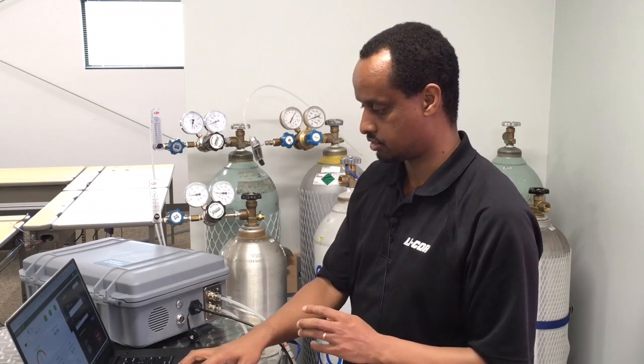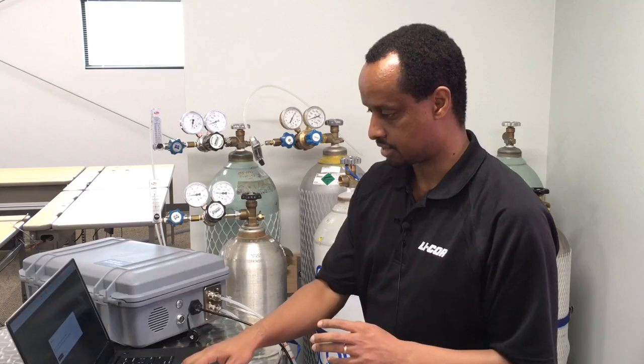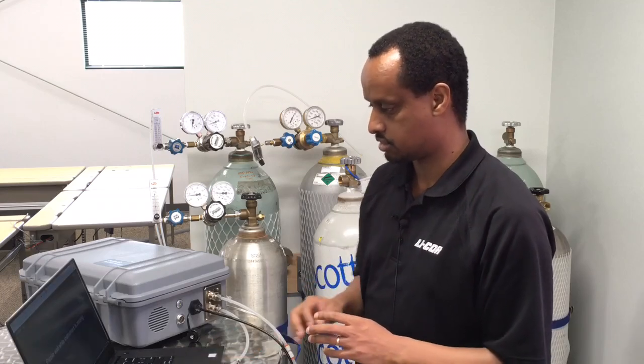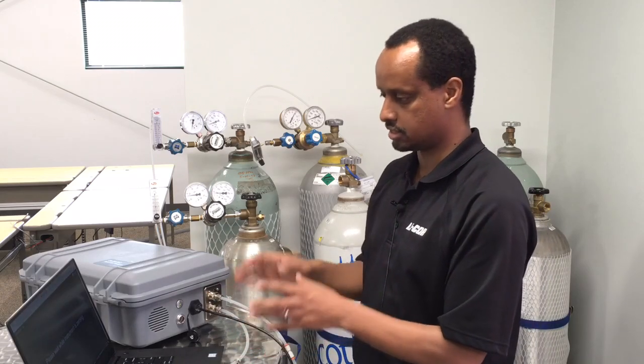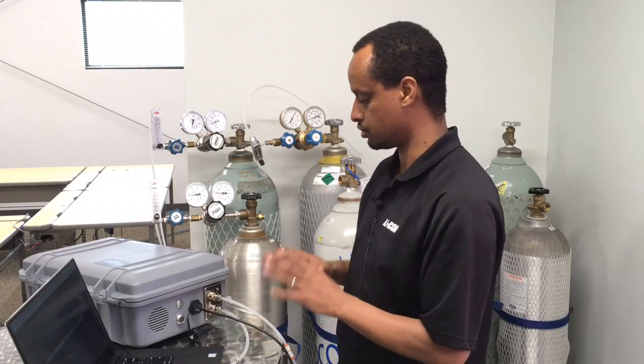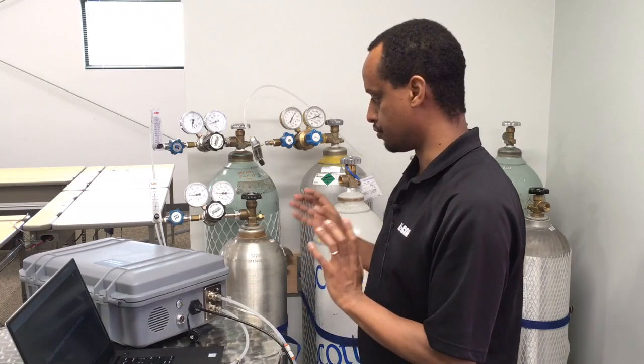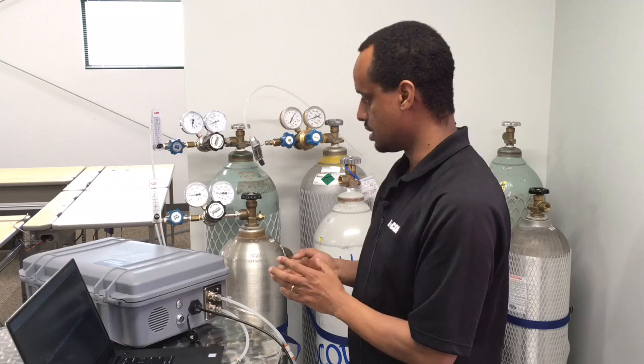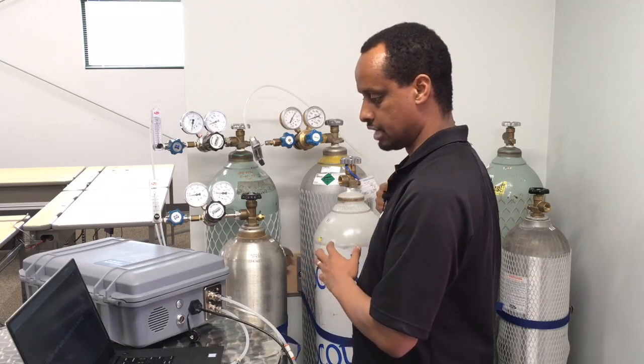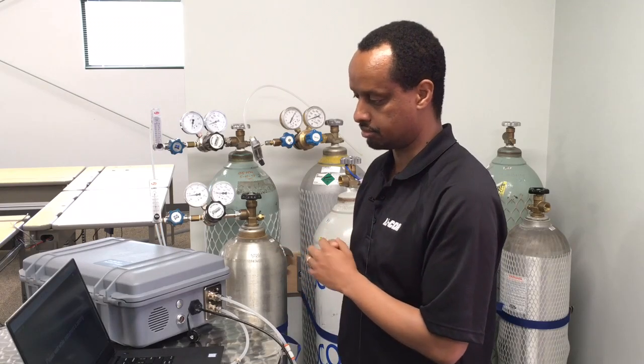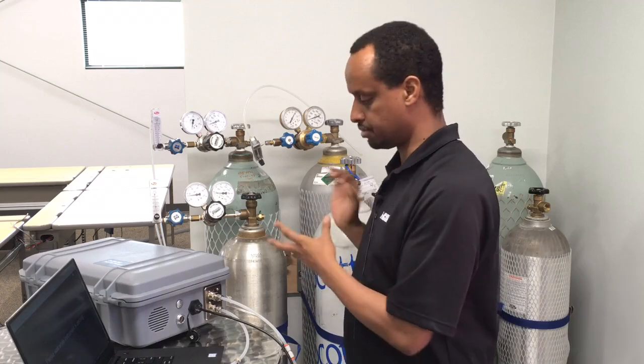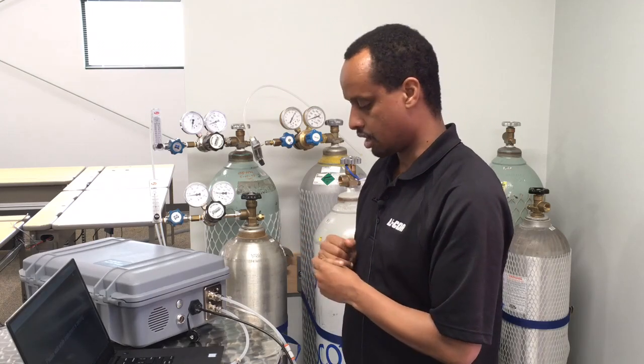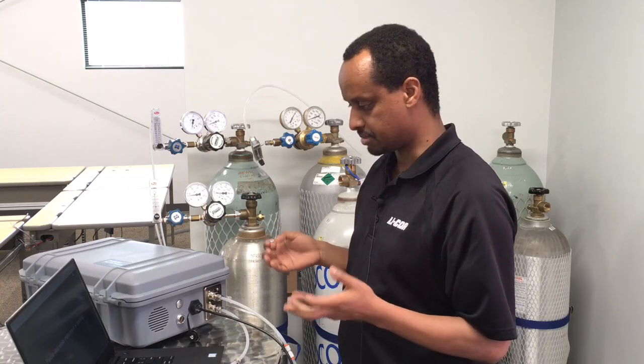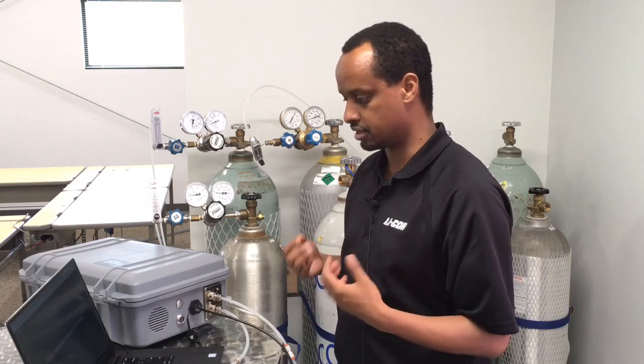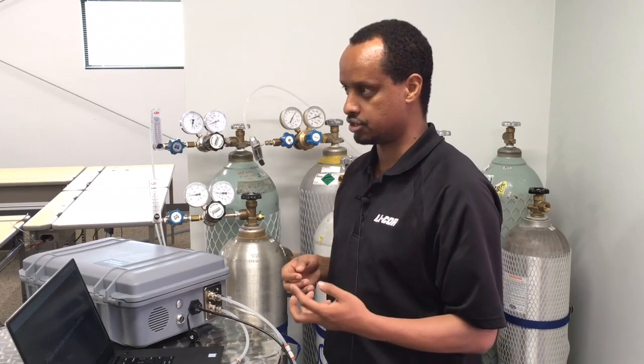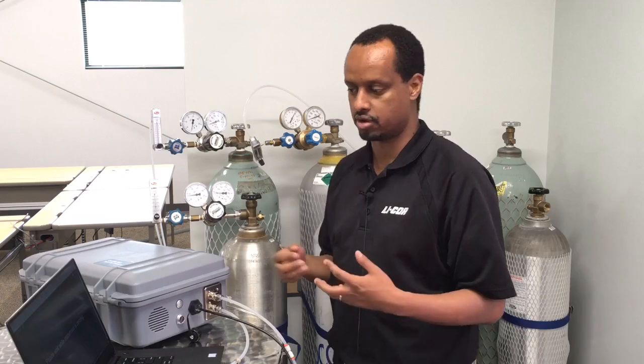So we'll go ahead and click 0, and it's going to ask us to confirm, and yes. And we see this screen where it says please wait while the instrument is zeroing. So we'll give it about 5 minutes to complete the 0 process, and in the meantime, you can work on getting your span tank ready, getting the plumbing for that prepared. And we don't expect the 0 drift on the instrument to be significant. Our specification says 1 ppb per 24-hour period.